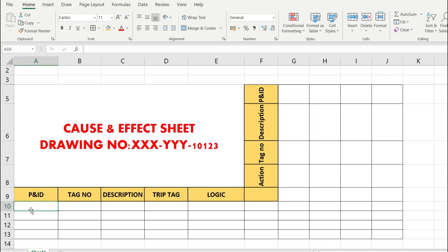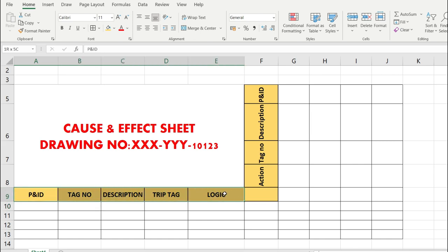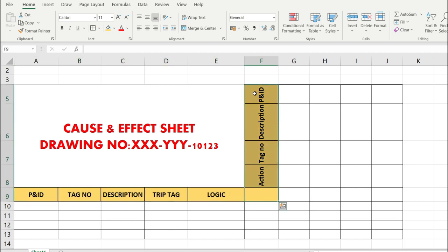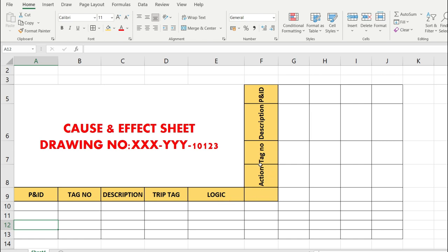This is the cause and effect sheet with drawing number XXXYYY-10123 — the number varies by organization. The horizontal columns represent the cause column, and the vertical columns represent the effect column. The cause column contains the P&ID tag number, description, trip tag, and voting logic. The effect column contains the action tag number, description, and P&ID reference.